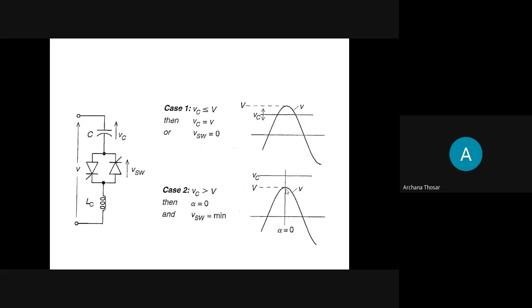Now there is another type called the fixed capacitor thyristor controlled reactor type VAR generator. Here, with this topology, the capacitor is fixed, and you only change the L by switching these two devices. So since the capacitor is fixed, the operation is quite simple.